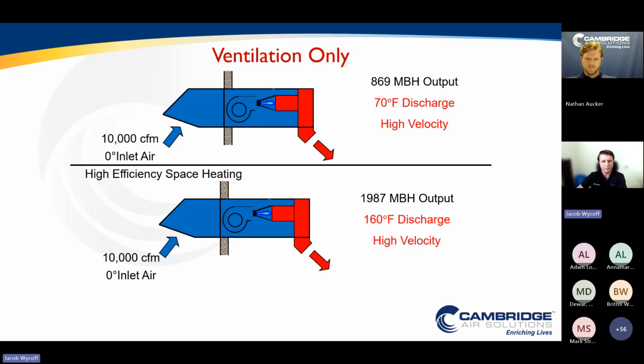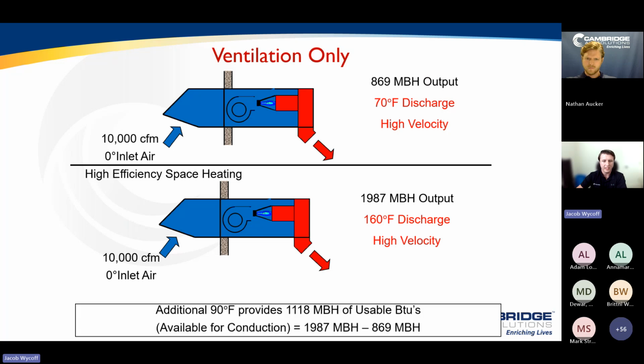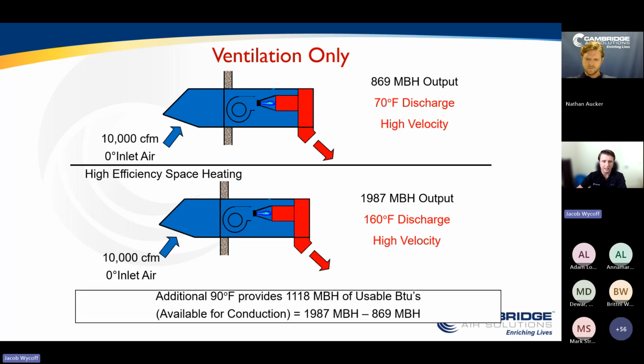So take that same example we had previously of a 70-degree discharge unit. It had 869 MBH of heat output. If we raise that discharge temperature all the way up to 160 degrees, you can see now we have 1987 MBH of heat. That difference between 1987 and 869 MBH due to raising the discharge is going to give us, in this case, 1100 MBH of usable BTUs because we're raising that discharge temperature by an additional 90 degrees above the space temperature.